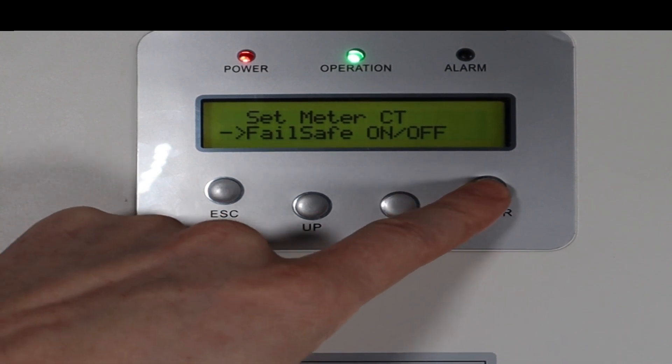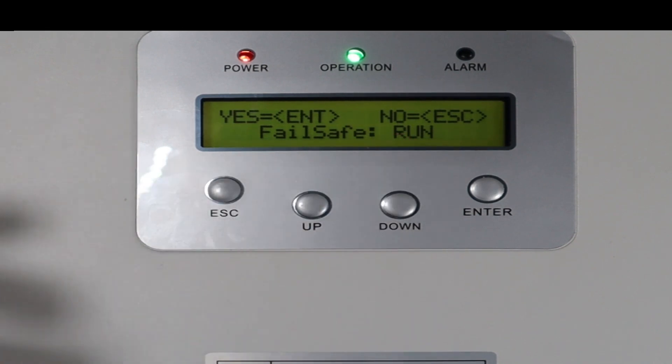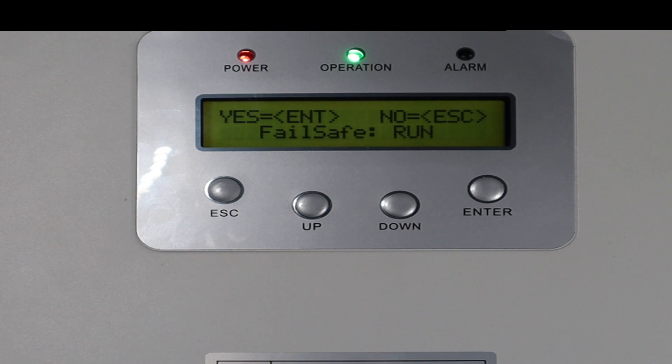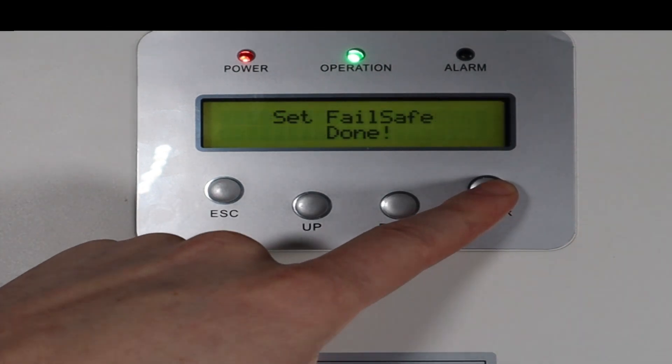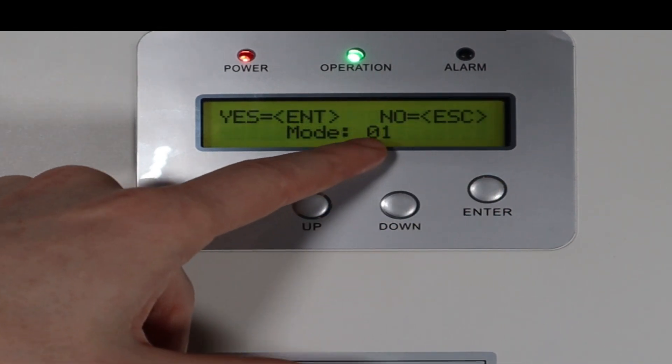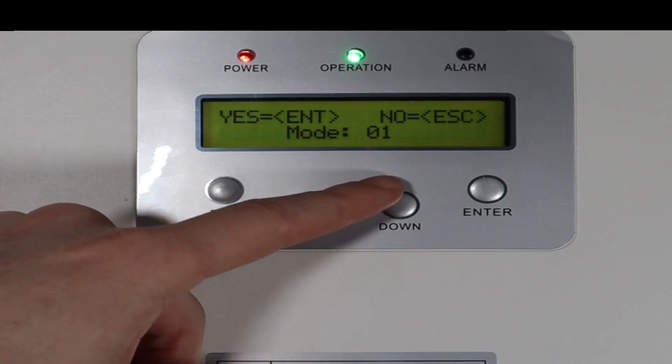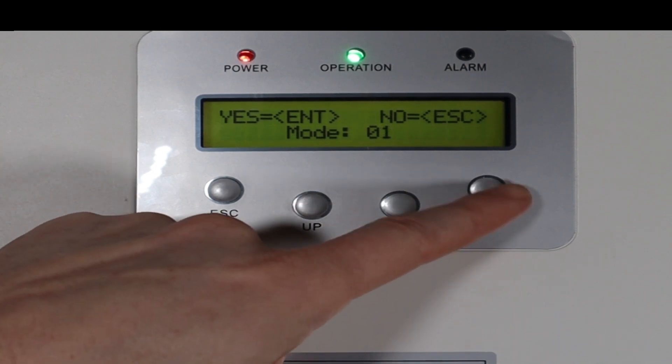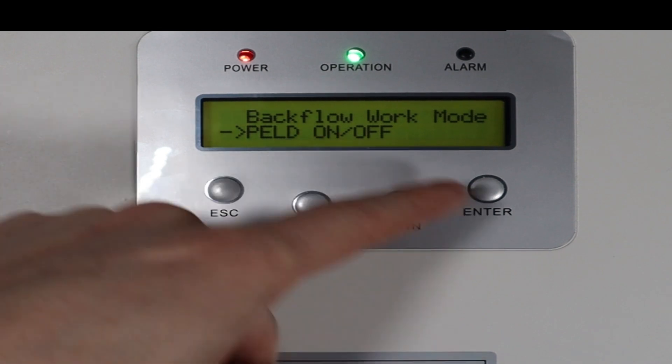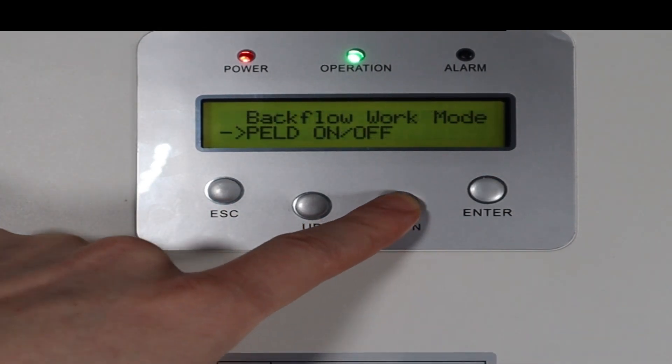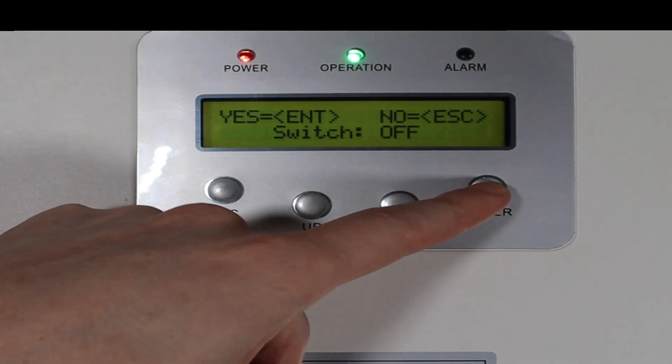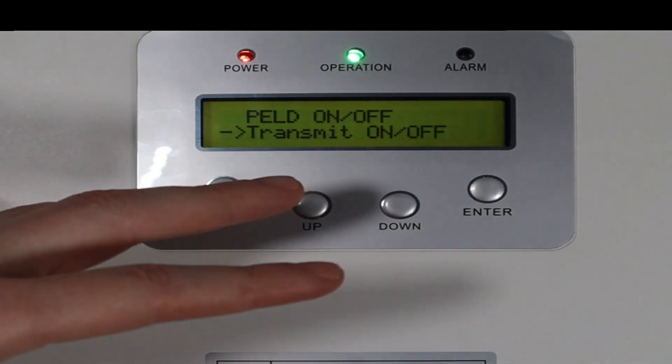Failsafe on off. So you would enable this to run. Essentially, it's very important that this EPM is tamper proof. And when a CT breaks or communication breaks, this system needs to go into a failsafe. So it's a good idea to set that to run. Setting backflow work mode. For most installations, you would stick with the default of 1. If you had per-phase limiting requirements, you could change that to 2. For more details on that, just refer to the user manual. But work mode 1 in most cases is perfect. PELD, it stands for Power Export Limitation Device On or Off. Go to that and switch it on. And then transmit on and off. Just leave that as default, as off. Or don't even go into it. It's essentially a debugging thing to let you program the inverters through the EPM.